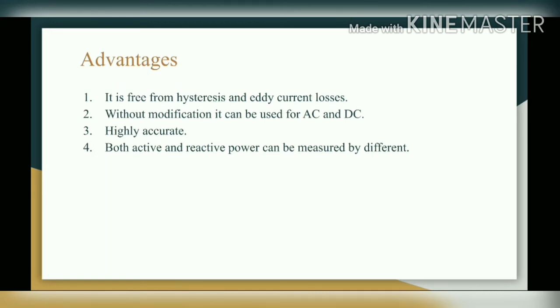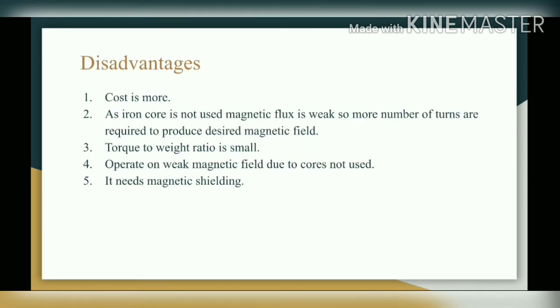Advantages: first, it is free from hysteresis and eddy current losses; second, without modification it can be used for both AC and DC; third, it is highly accurate; fourth, both active and reactive power can be measured by this wattmeter. Disadvantages: first, cost is more; second, as an iron core is not used, the magnetic flux is weak, so more turns are required to produce the desired magnetic field; third, torque to weight ratio is small; fourth, it operates on a weak magnetic field; fifth, it needs magnetic shielding.